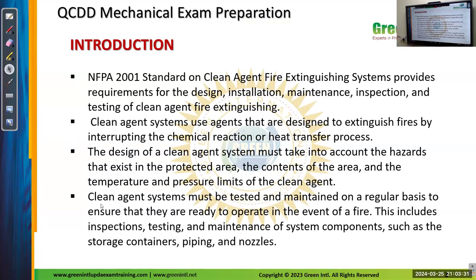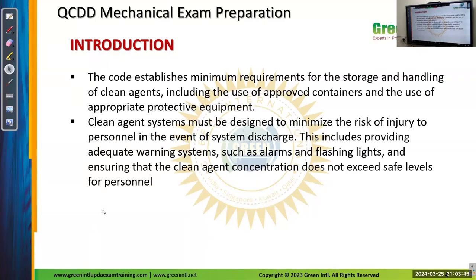The design of a clean agent system must take into account the enclosure's area and temperature. Clean agent systems must be tested and maintained on a regular basis to ensure the operation is working or not. So the code establishes minimum requirements for the storage and handling of clean agents, including the use of approved containers and the use of appropriate protective equipment. Clean agent systems must be designed to minimize the risk of injury to personnel in the event of system discharge. This includes providing adequate warning systems such as alarms, flashing lights, and ensuring that the clean agent concentration does not exceed the safe level.